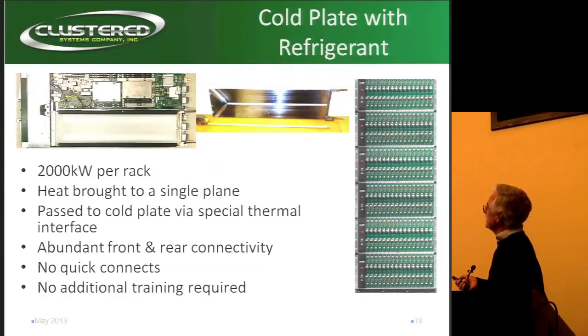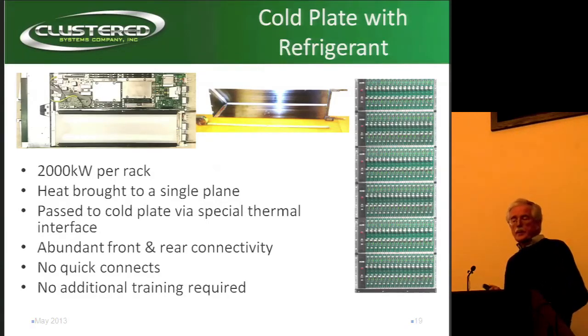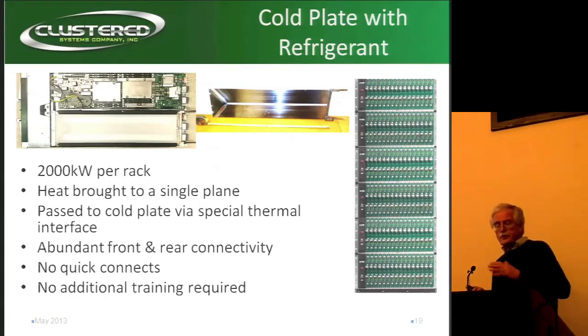These are the heat risers here. And as you can see, these are the DIMMs as well — essentially standard DIMMs. We have a supplier that actually designs the DIMMs with a jacket that is very flat on top so it's easy to cool them. The only other thing we need is on the chipset — another little cooling block. We go through and measure the heat dissipation of the various units and figure out what needs to be cooled.